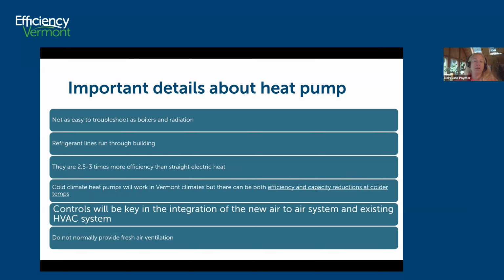Controls can be really complicated when you're trying to integrate your new heat pumps with your existing heating system. So your existing heating system could be boilers with baseboard. They could be space Rinnai heaters. They could be a rooftop unit. It could be unit heaters. So the key is to link those together so that when your heat pump is running as your primary heat, you have a way in which to signal to bring on the secondary heat. And does that mean your heat pump shuts off altogether and you just switch over to the other system, or does it supplement? So these are the types of things that a person has to work out. And in commercial buildings, it can be fairly complicated and it can add cost to your project.